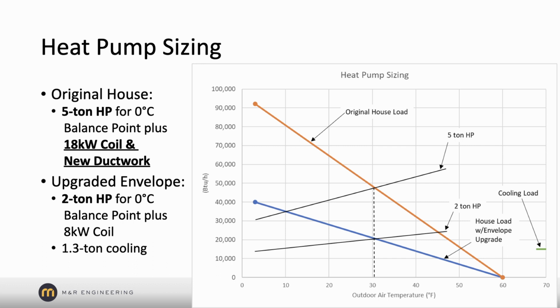So the orange line here is the heating load based on the outside air temperature, which is on the bottom x-axis. And the blue is what the heat load would be with the envelope upgrade. So it's more than cut in half with the envelope upgrade I'd done a couple of years before. I would have needed a 5-ton air source heat pump if I didn't do anything, but instead I just needed a 2-ton. And on the far right, you'll see the cooling load, and my cooling load was about 1.5 tons.